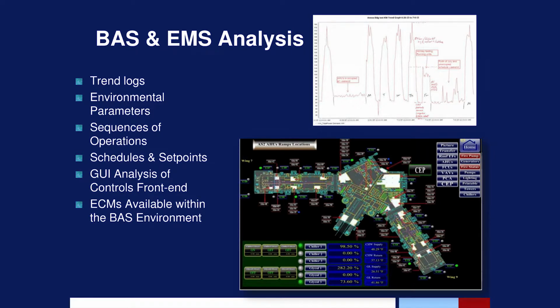Are they really maximizing the benefit of that control system? Does it have all the information in there that really ought to be in the one-stop shop your control system could be? Things like equipment nameplate data, make, model, serial number, refrigerant charge, amp draw, that type of stuff you see on the equipment could be on the equipment graphics as well, so a new service tech coming on board doesn't need to hunt for that information anywhere. Same thing with factory service manuals, bill of materials, and as-built documents. These are all suggestions to be rolled in and implemented into the building automation system.